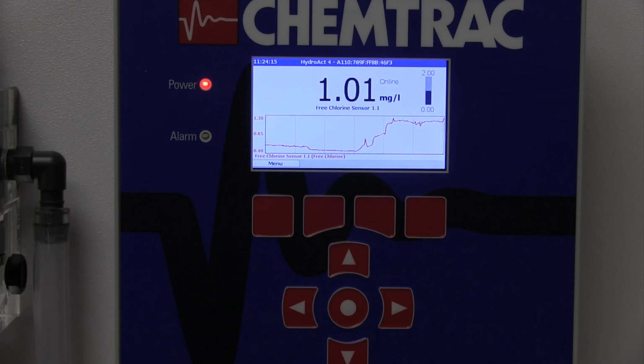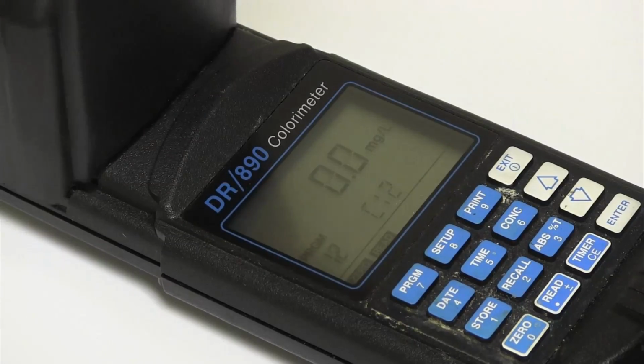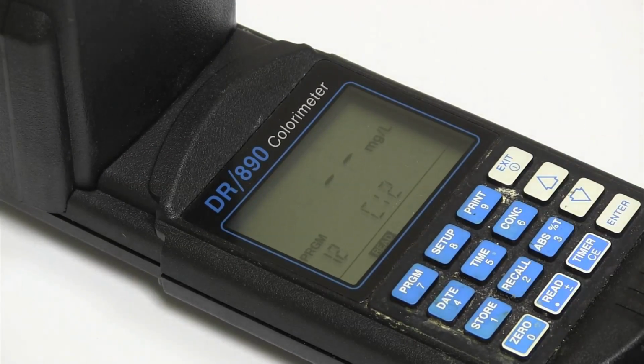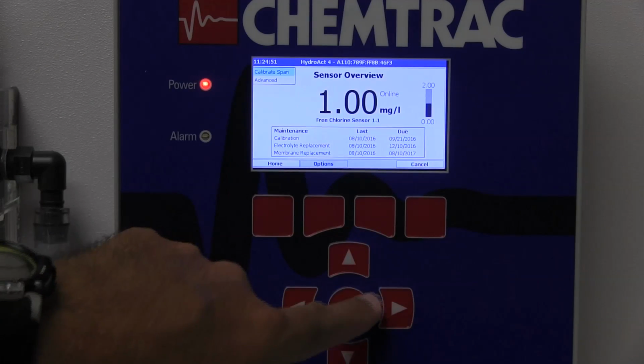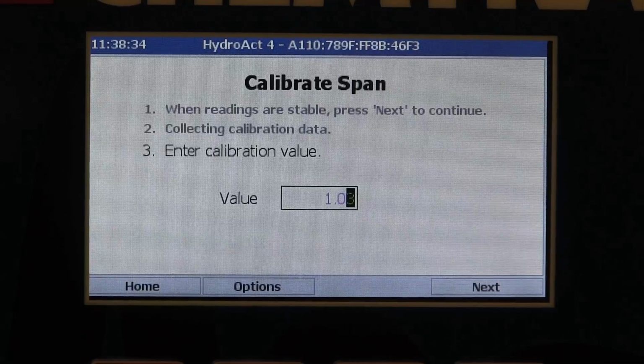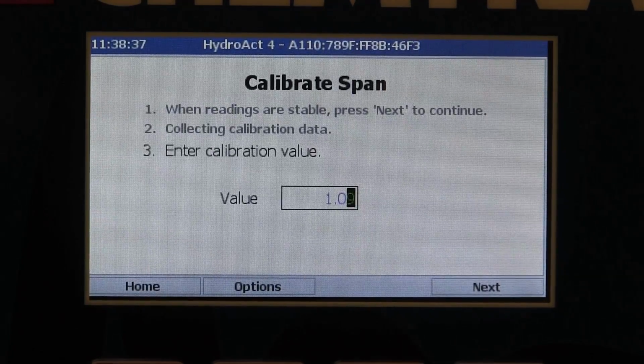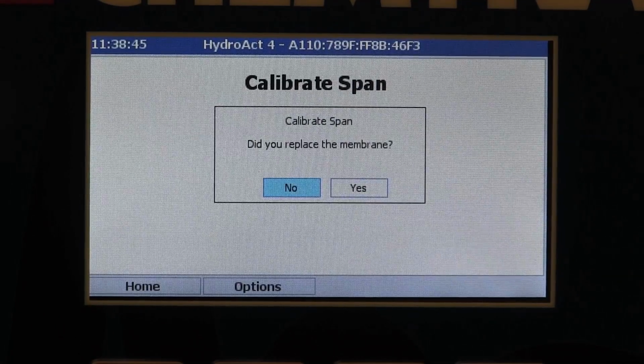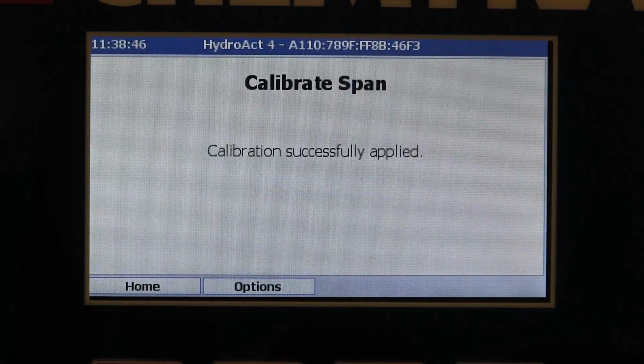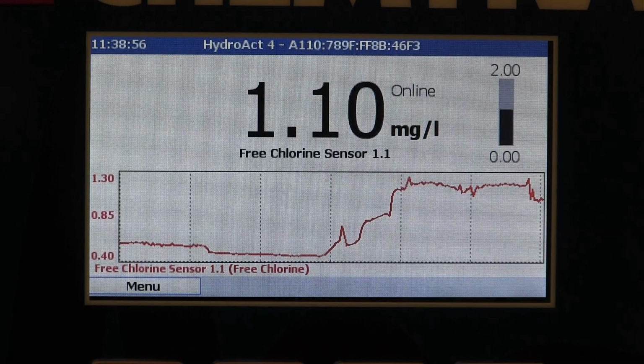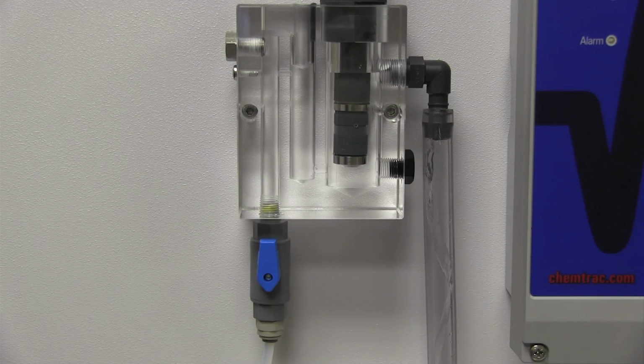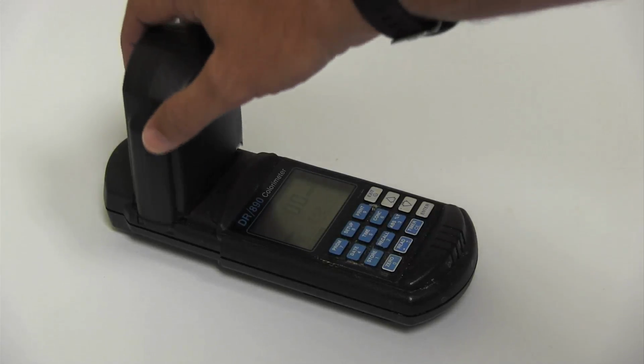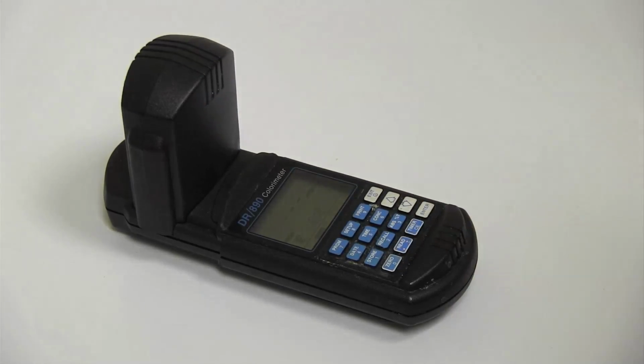When calibrating, the reading from the analyzer is compared to that of another measurement method, such as a DPD chlorine test. At least 2 DPD tests should be performed in order to ensure repeatability. The calibration mode on the analyzer is easily accessed, and the chlorine reading is adjusted to match the results of the DPD test. Whenever a new membrane cap is installed, it is recommended to do an initial calibration after 2 hours and a second calibration the following day. The probe can be expected to maintain accurate readings for up to a month, although it is recommended to check the calibration weekly.